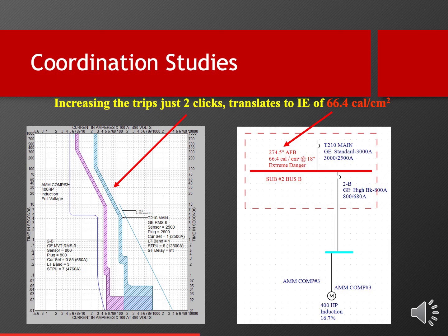And if they dial that up just a couple of clicks on the current, they didn't take it all the way back to maximum settings, look at what happened to the incident energy. It went from 2.9 calories to 66.4 calories. Now, 66 calories is pretty much certain death if you get exposed to that amount of current and the blast associated with it. And what's so important about this is that this is actually a study I did myself.